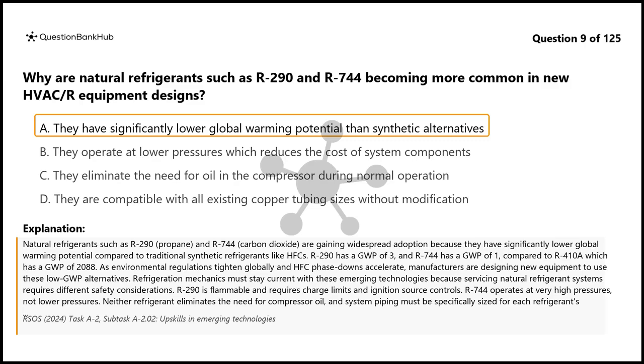Refrigeration mechanics must stay current with these emerging technologies because servicing natural refrigerant systems requires different safety considerations. R290 is flammable and requires charge limits and ignition source controls. R744 operates at very high pressures, not lower pressures. Neither refrigerant eliminates the need for compressor oil, and system piping must be specifically sized for each refrigerant's properties.